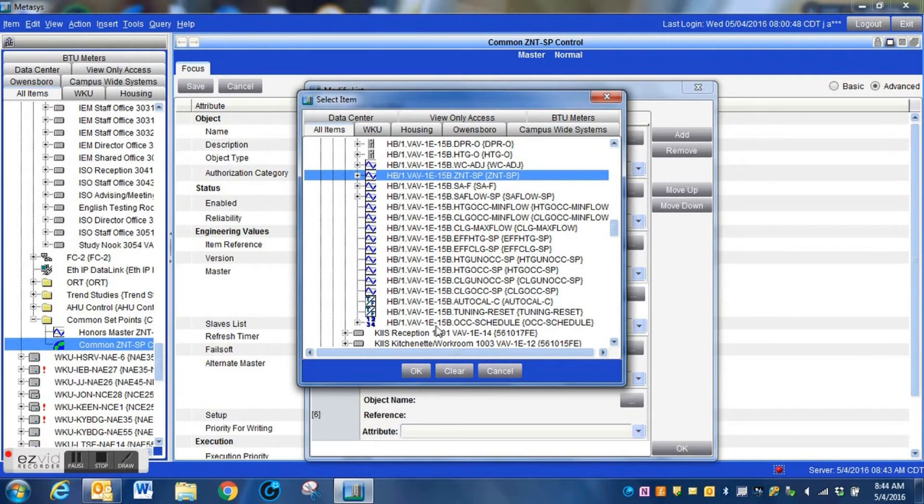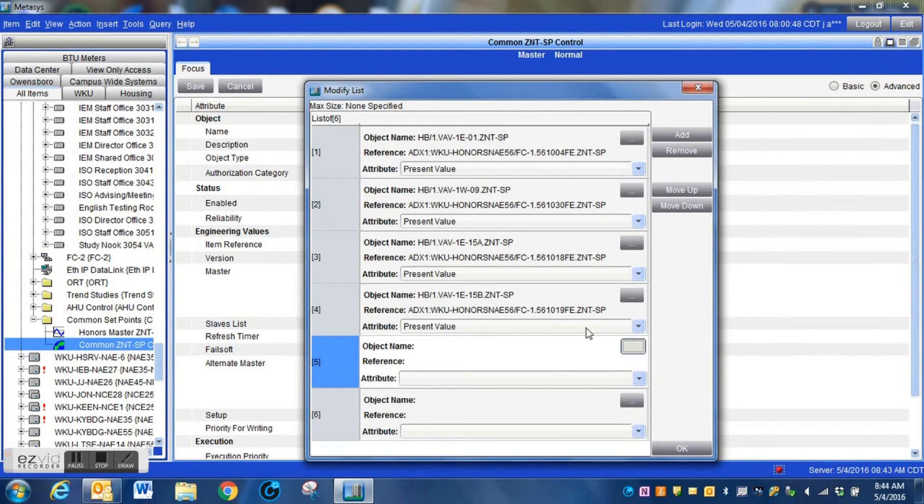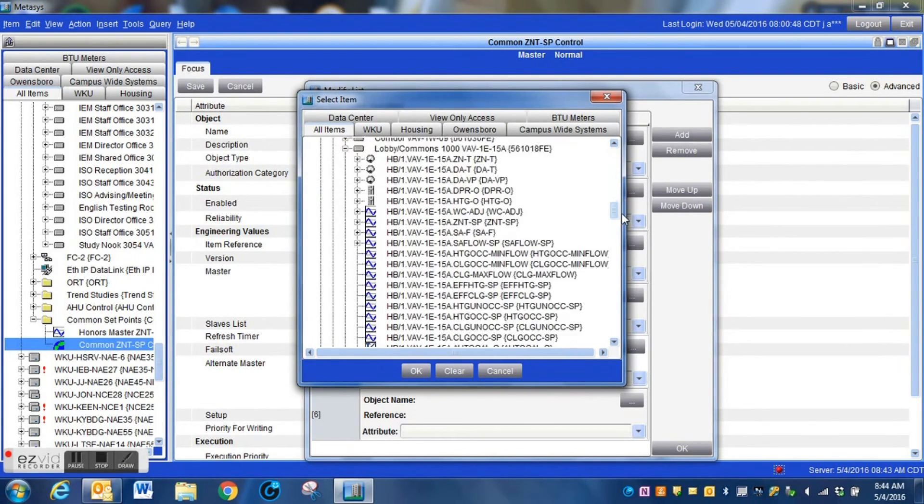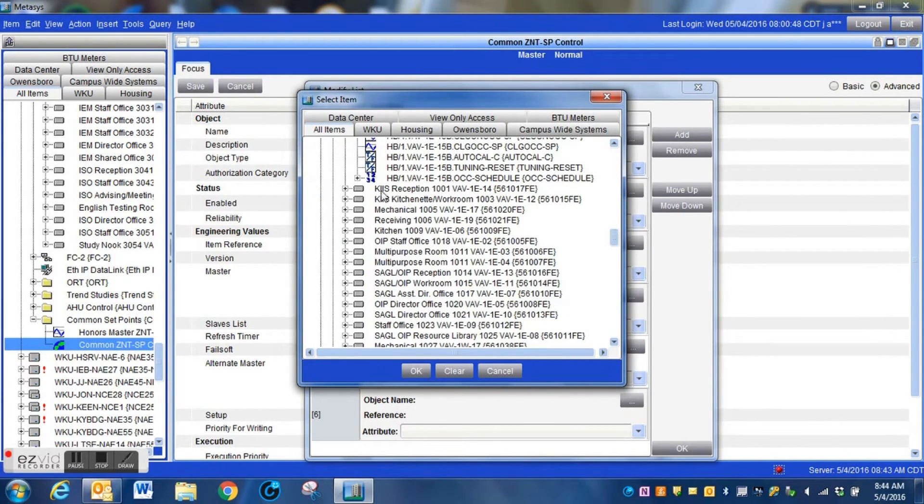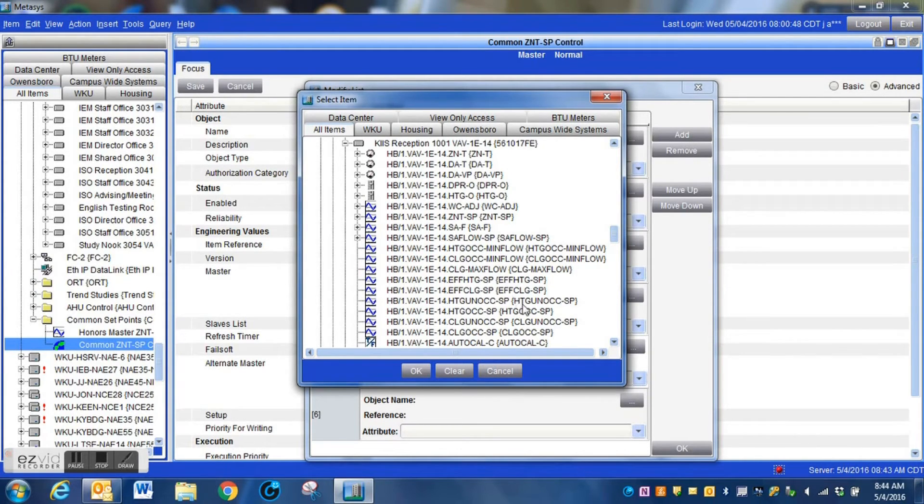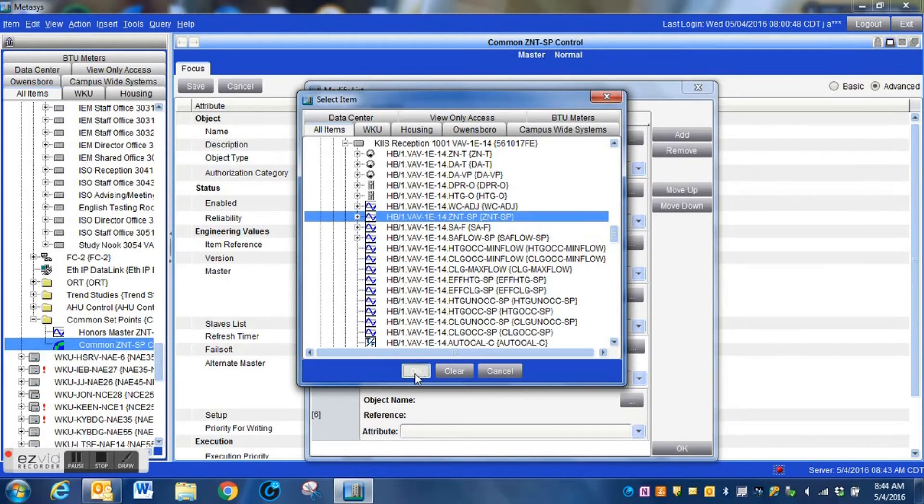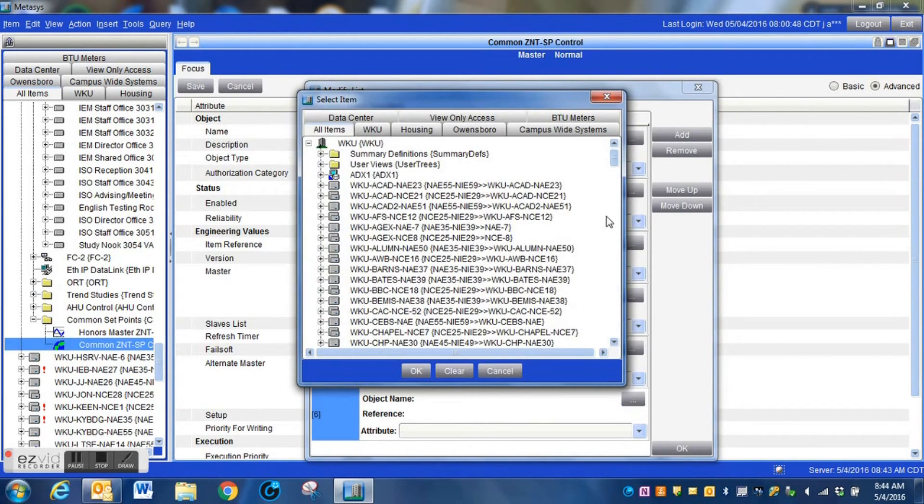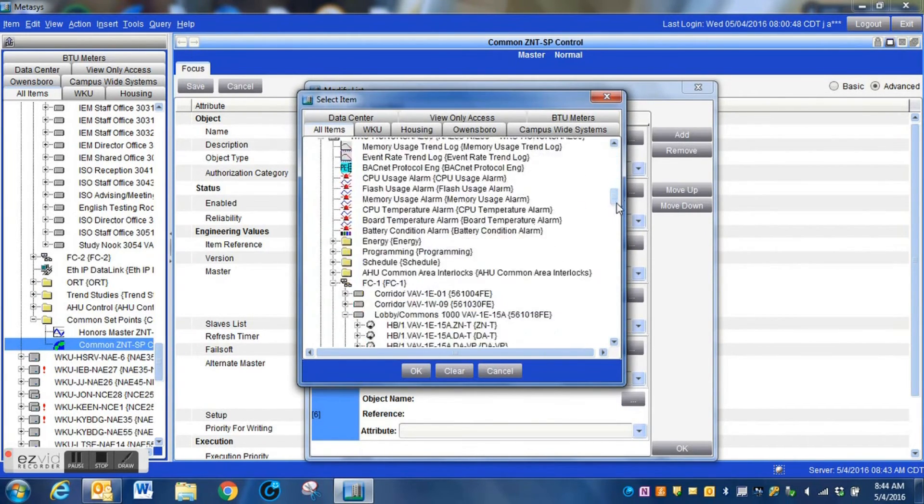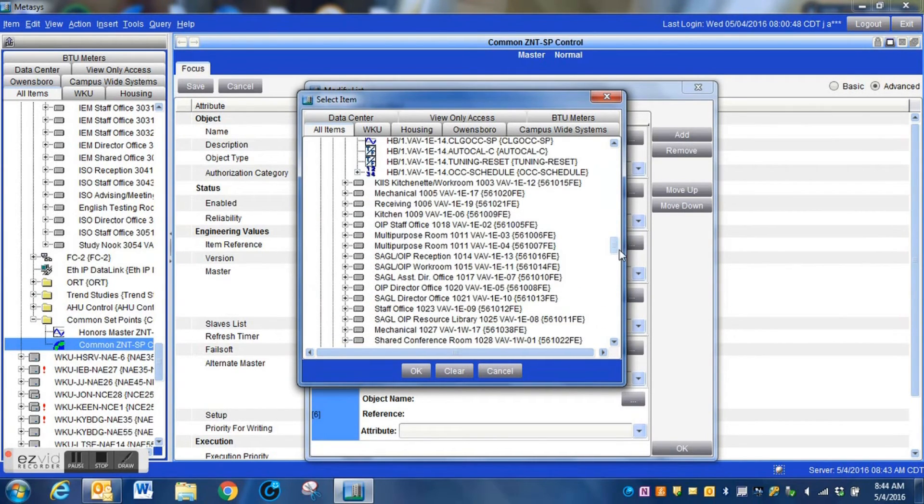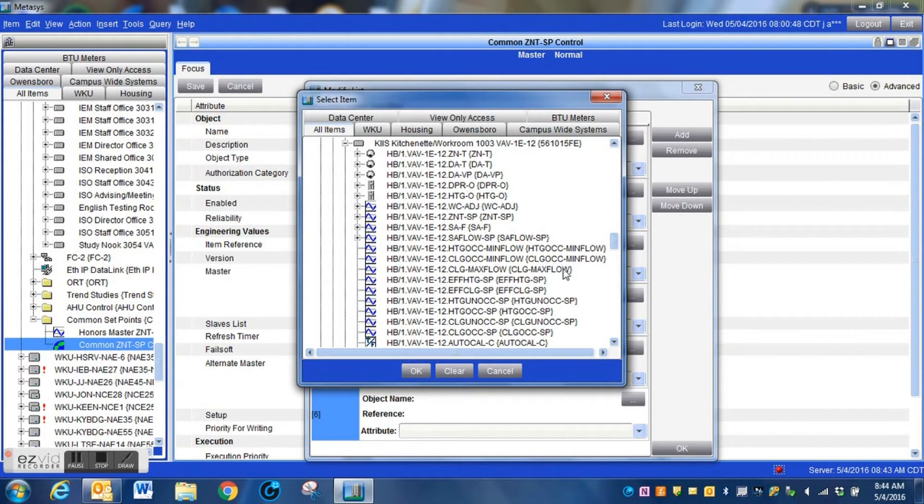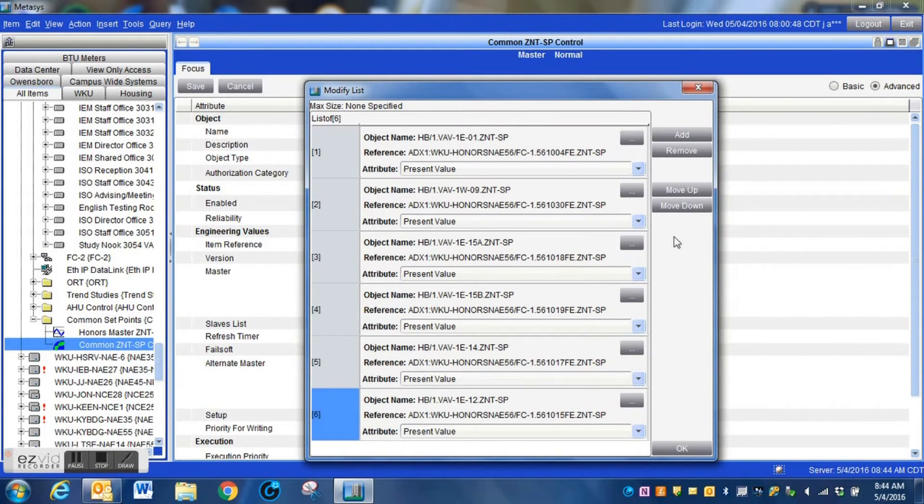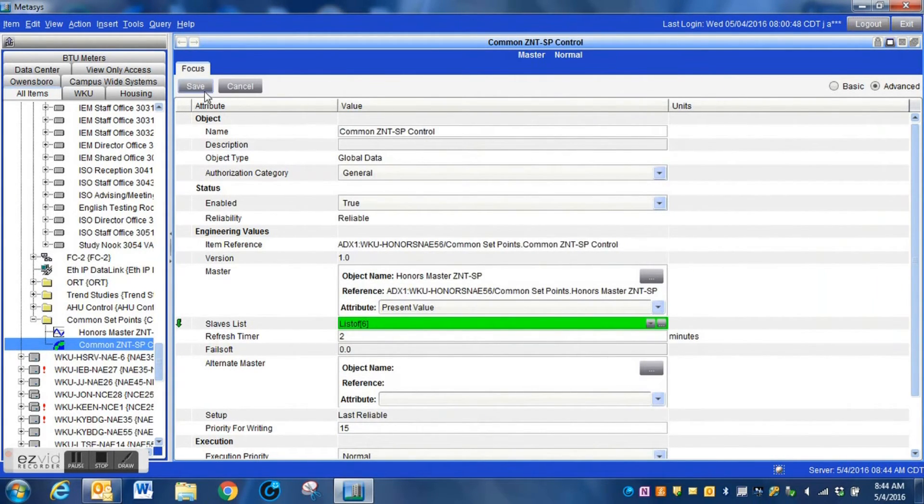The way that you link each of those, it will follow that slave list and write that value into each one of the controllers. You can see here, we're just continuing adding the VAVs for this process. You can't add multiple. Unfortunately, it's a one at a time process. But it really does help your system. This building automation is what it's about. A little bit of work now pays off later. It simplifies things, makes things go a little bit smoother for us. That's a lot of what we do. We try to make the things work smoother, we try to let the technology do our work for us.